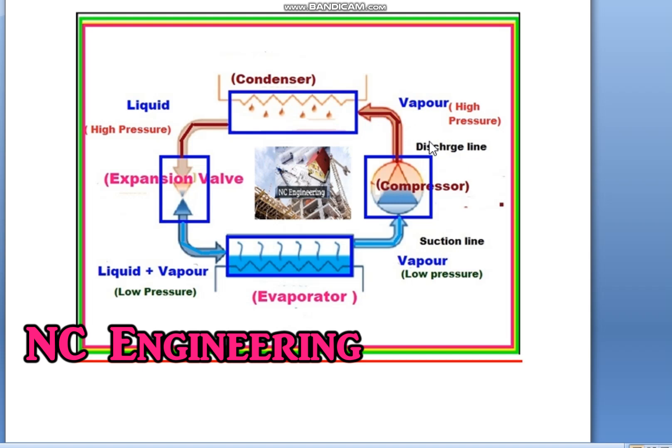Air-cooled condensers come in two types. For very small applications we use natural air — like a refrigerator — where the condenser has only coils and is cooled by natural air. Whereas for air conditioners and chillers, we have a blower to blow the heat through the coils. Inside the condenser, the refrigerant enters as high pressure vapor, gives out its heat to the surrounding, and comes out as high pressure liquid.